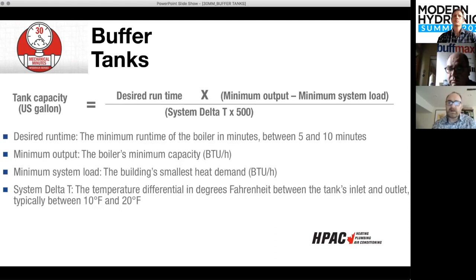Now, what's my smallest load that's connected to that system? If I've got a house with 10 zones and one of them is just a small bathroom or a small room, if a single zone is calling, that single zone might have a load on a mild day of maybe 2,000 BTUs. So if it's running at 2,000 and my boiler can only fire at 10,000, my boiler is making 5 times as much energy as I can take away. So the boiler is going to basically go off on its limit very quickly if I don't have a buffer. So that's what we're trying to do when we size it.